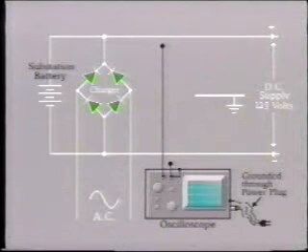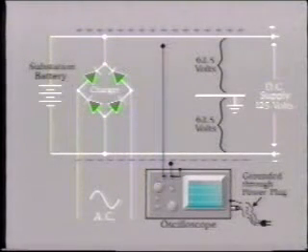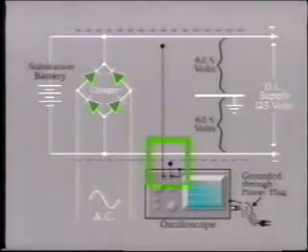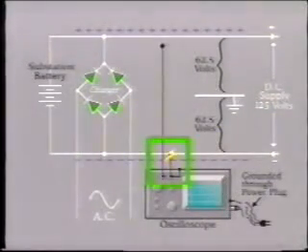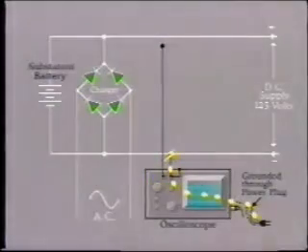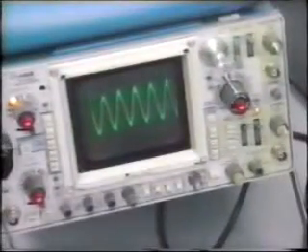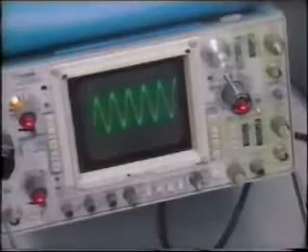The capacitance between the DC cables and ground causes ground to be at a potential halfway between the positive and negative feeds — say, 62.5 volts DC. As soon as the grounded scope chassis is connected to the equipment under test, this capacitance discharges through whatever components the reference lead is connected to and can cause catastrophic failure. On a telephone circuit, it may cause common mode voltages to be coupled to the phone line via the scope, perhaps disrupting SCADA communications or causing unexpected operation on a pilot protection scheme. Whenever making tests on solid-state or telephone equipment, be sure to use some form of isolation, such as an input isolator, to isolate the scope probe from ground.